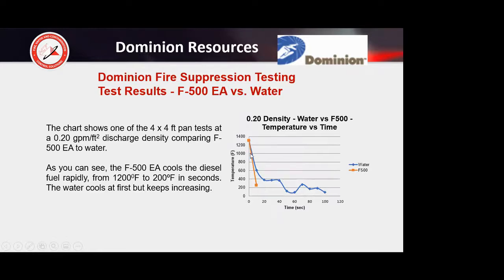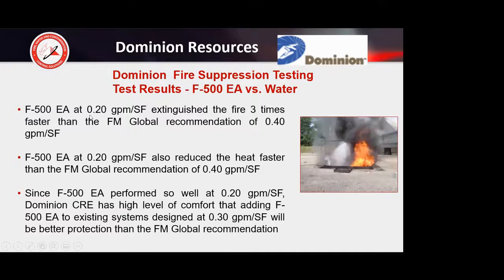So this shows the very rapid temperature reduction versus plain water. Here, when they turn the sprinkler off, you get your typical hump back where it's coming way back up again. So you don't get the hump back with the F500, because once it puts the fire out, the solution continues to absorb heat rather than allowing the heat to come back. So here was the difference: 0.2 versus 0.4 was 3 times faster, also reduced the heat more.